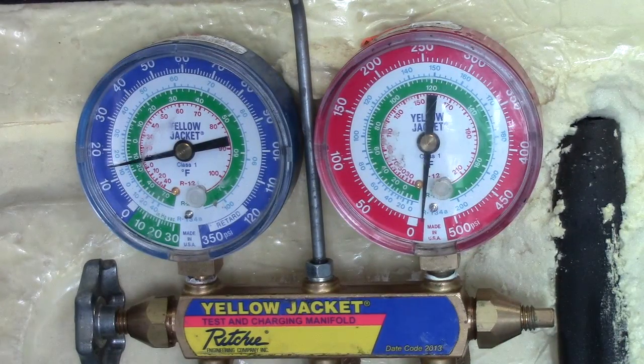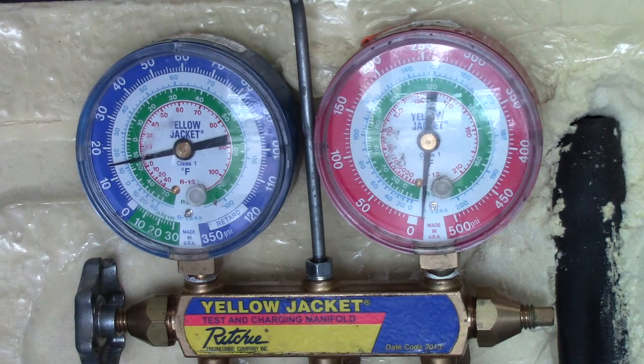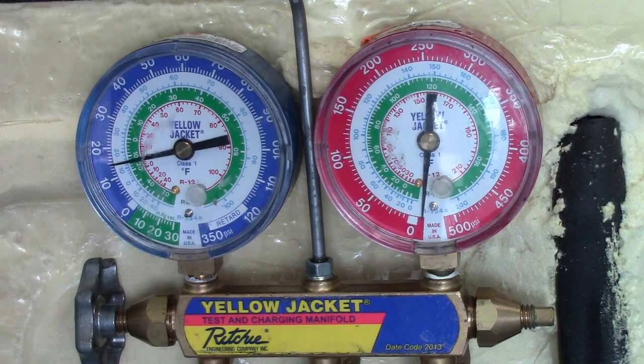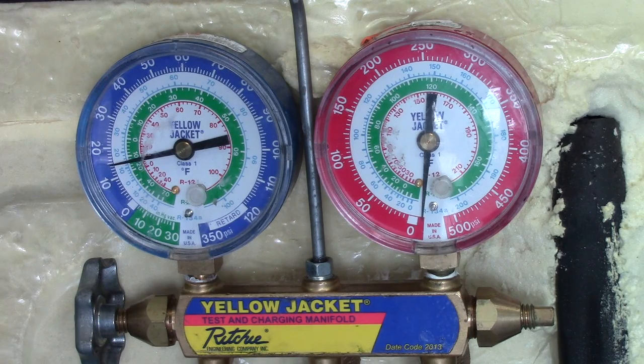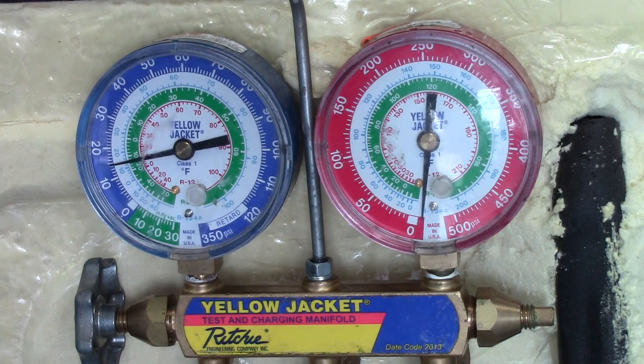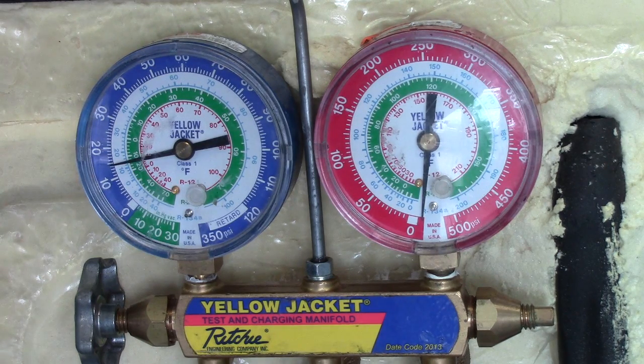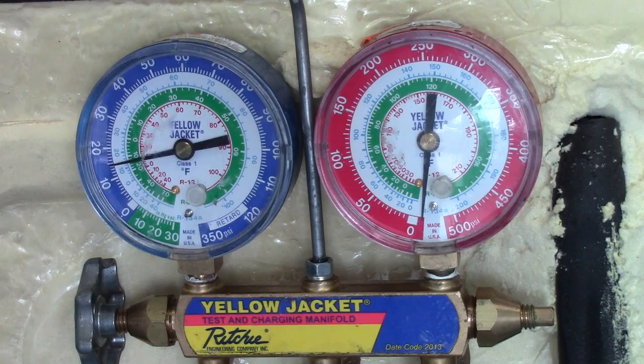Okay, it's been sitting overnight now and as you can see it's right about 15 pounds of pressure. That's right where I left it yesterday. So if there is a leak in this system still, it's going to be such a micro leak that we'll never be able to find it. So now that we have it all filled up, charged up, it's cooling good, we're just going to put it back together and it'll be good to go.